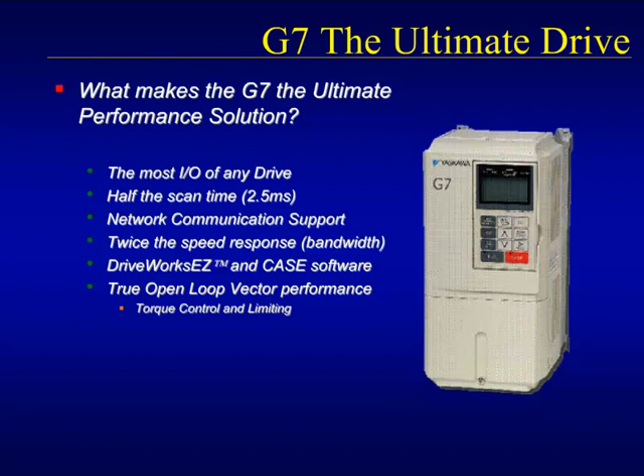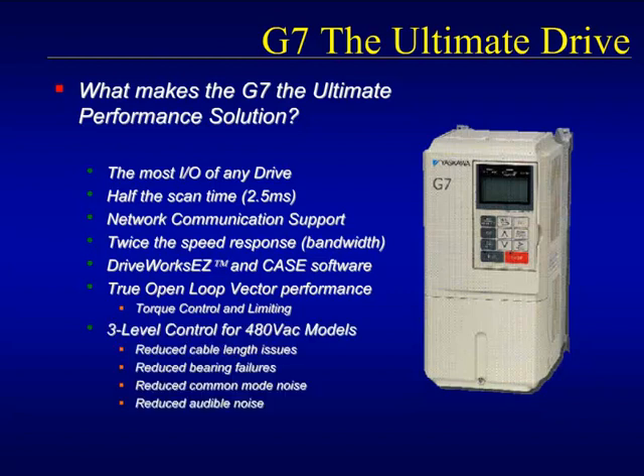Lastly, the 480-volt version of the G7 offers 3-level control that will reduce or eliminate long cable issues, reduce bearing failures due to bearing currents, and limit common mode noise, while also reducing the effect of audible noise.